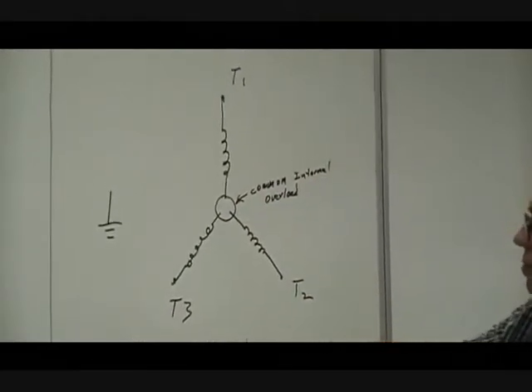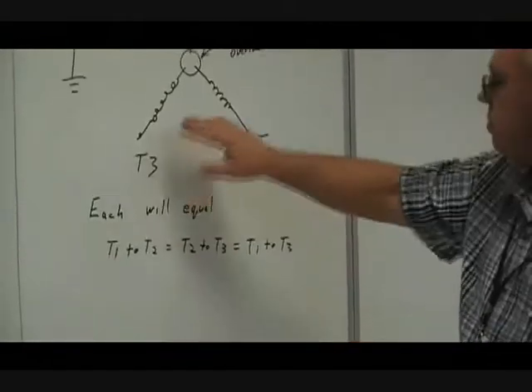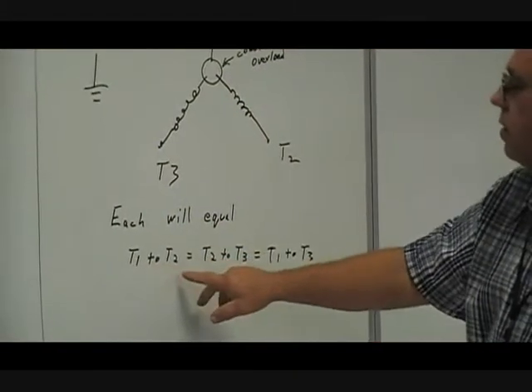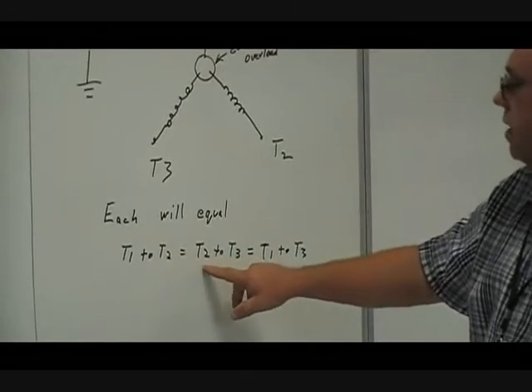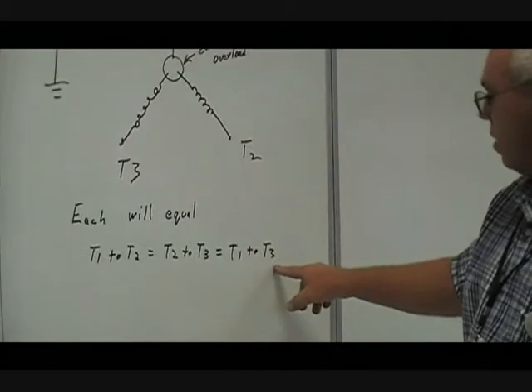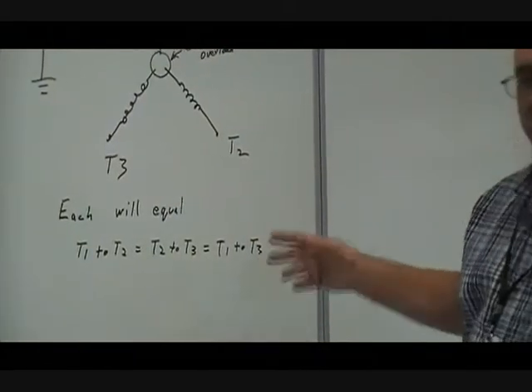If a good compressor should be so that each, from terminal to terminal will equal. In other words, T1 to T2 will equal T2 to T3, T1 to T3. In other words, anywhere you measure should be the equal resistance.